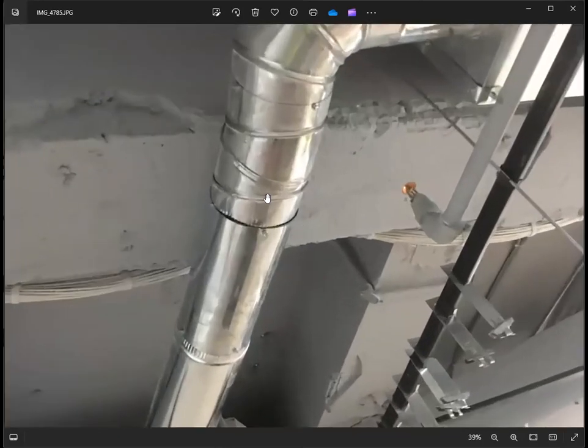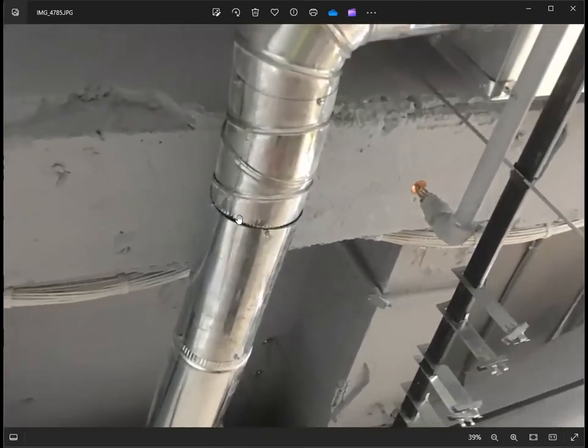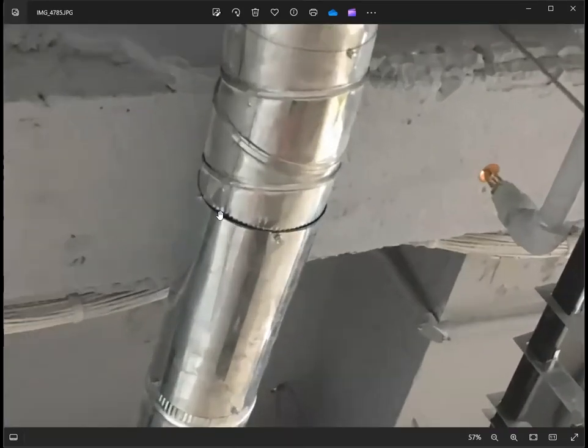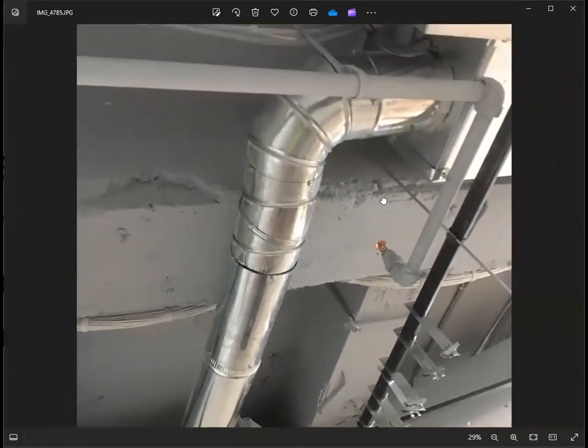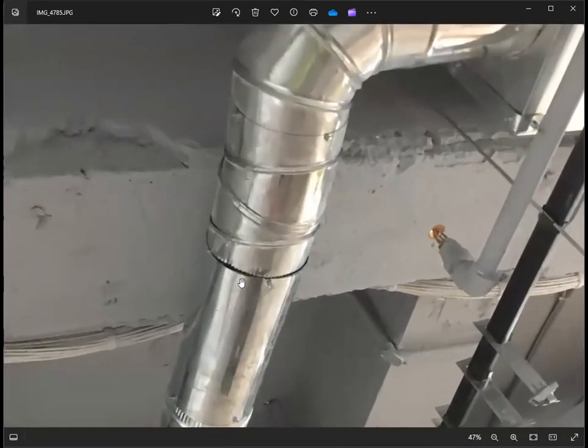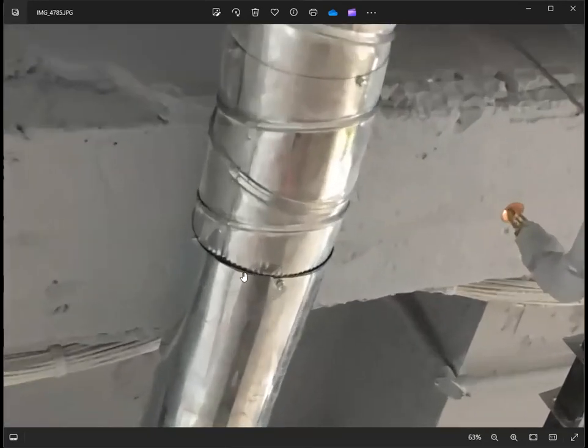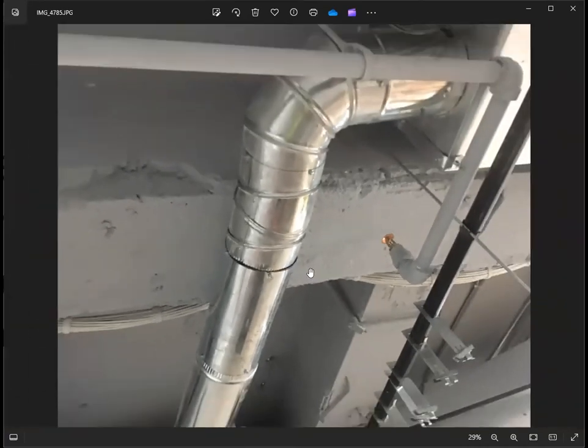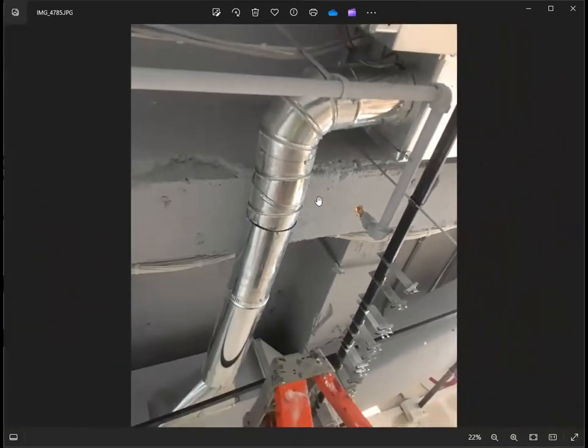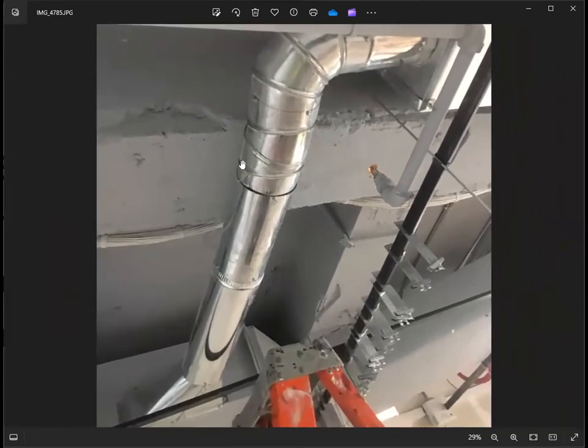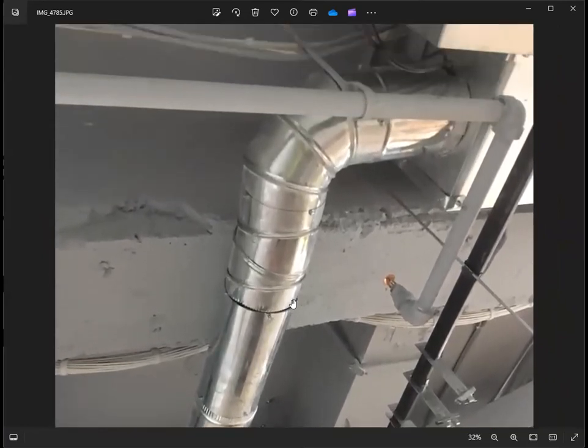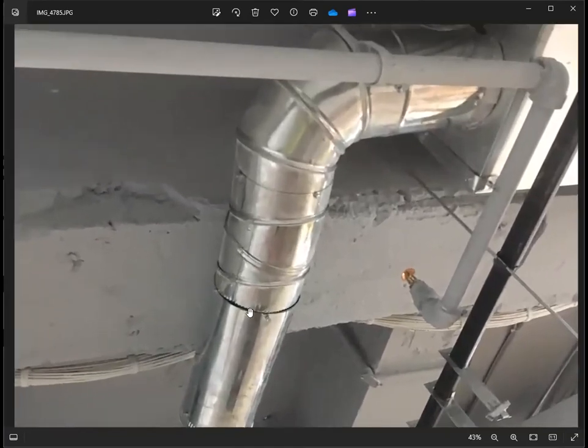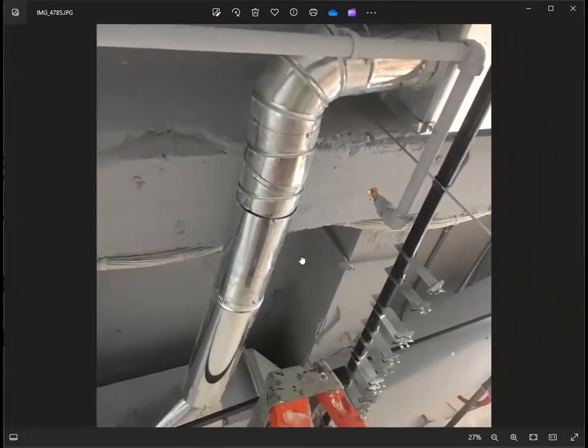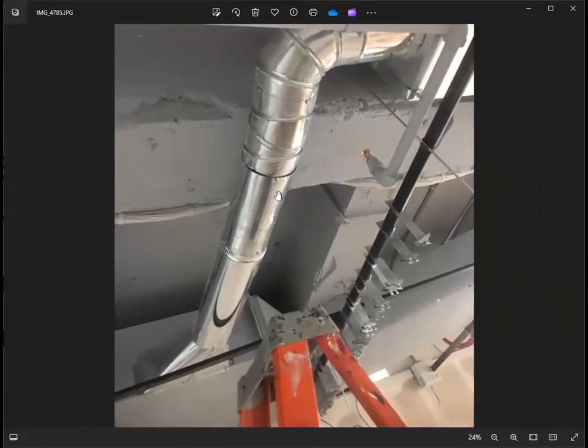And take note of the ductwork joint. So they need to seal this up. They need to have a sealing material, a mastic. The problem this will produce will be air leakages in the system. So before signing off the job, you need to make sure that the contractor will seal every joint, every connection, perfectly airtight to have an efficient system for the airflow.